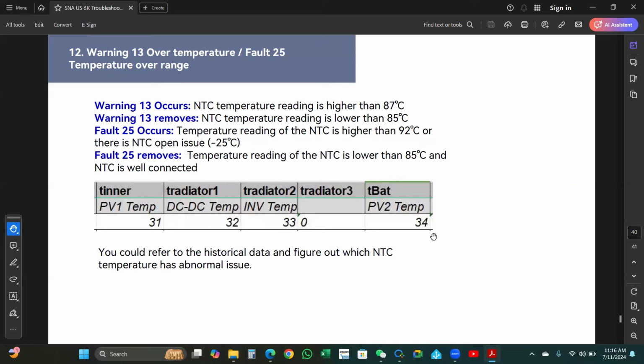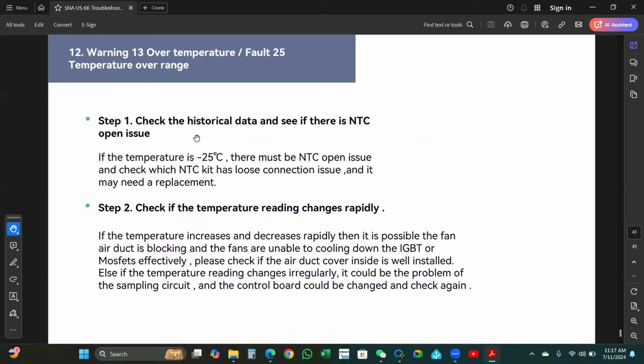This is where, if you look at the data history, this is what it means. You could refer to this historical data and figure out which NTC temperature has an abnormal issue. Step 1, check the historical data and see if there is an NTC open issue. If the temperature is negative 25, there must be an NTC open issue, so check with the NTC kit. It's a loose connection issue and it may need a replacement.